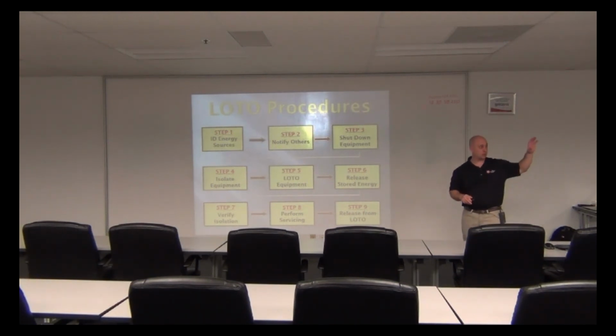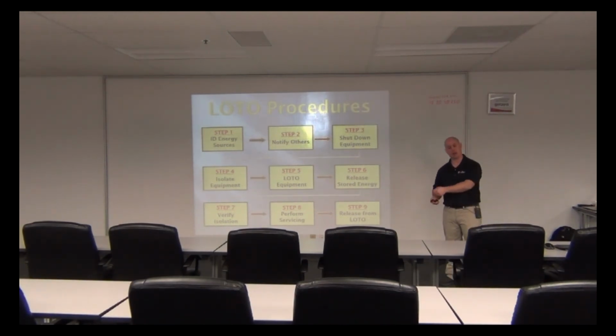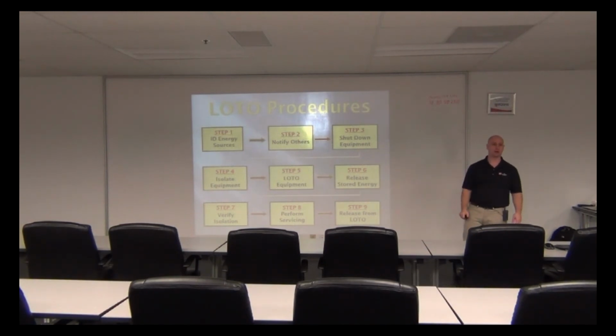If there's no power going to it and you used it for that reason to store something, which you're really not supposed to, but if you did, make sure when you power it back up, you take it off, because all of that could affect later on down the road. You got a panel, it's got something on it, someone needs to work in the panel, they're not thinking about what's on top of it. They open the panel, it falls out, goes in there while they're working on it, and an arc flash could occur because you made contact between phase and phase, or conductor and conductor, I like saying, because it just makes more sense to me.